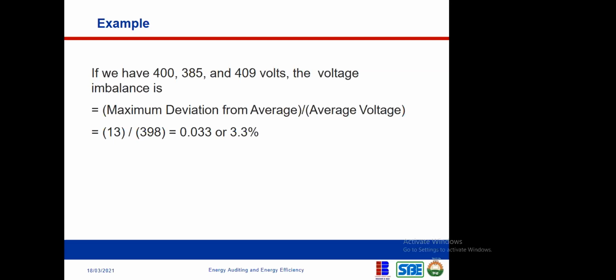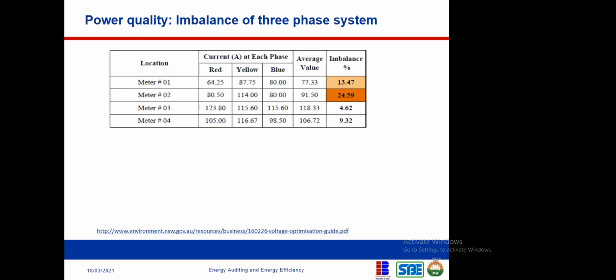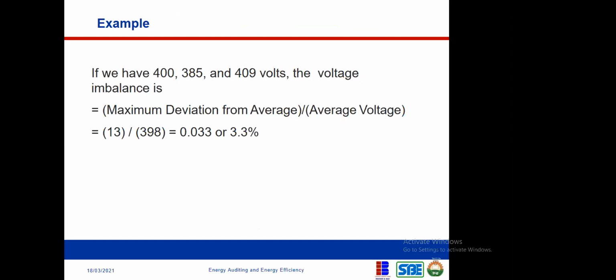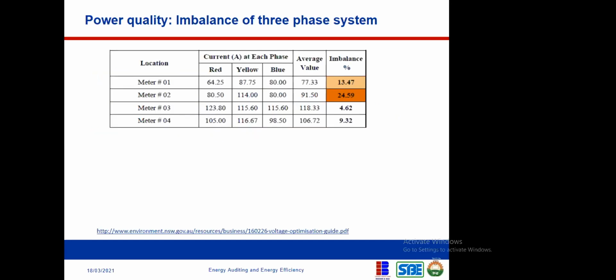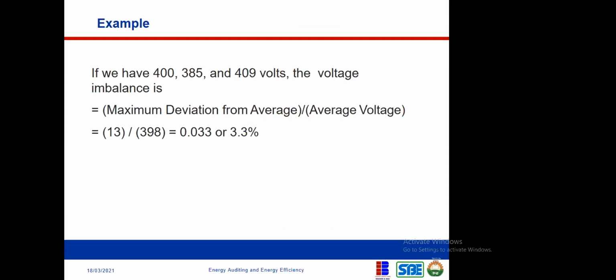So the maximum deviation from the average is 13. How do we arrive at 13? We determine the average of the three voltages, which is 398. When you subtract that from the three voltages of the three lines, 400, 385, and 409, the highest difference you get is 13. So when you divide 13 by 398, you get 0.033. When you convert that to percentage, you have 3.3. So the voltage imbalance is 3.3%.